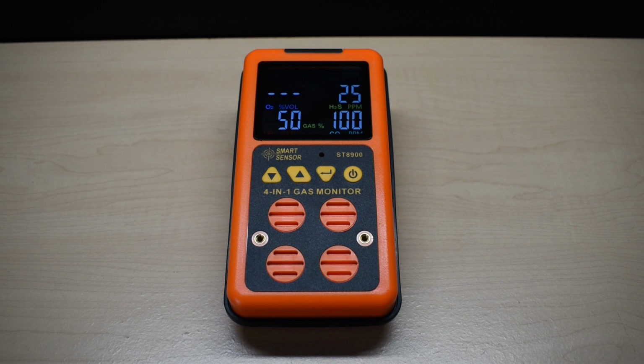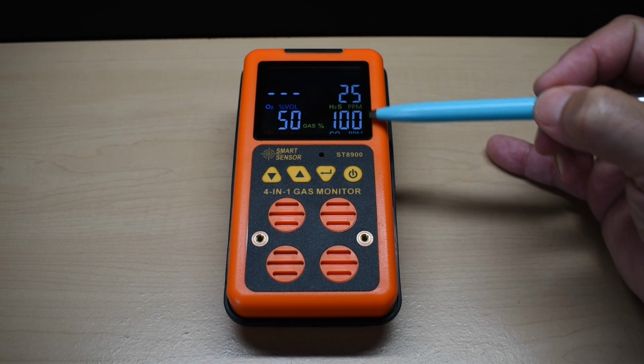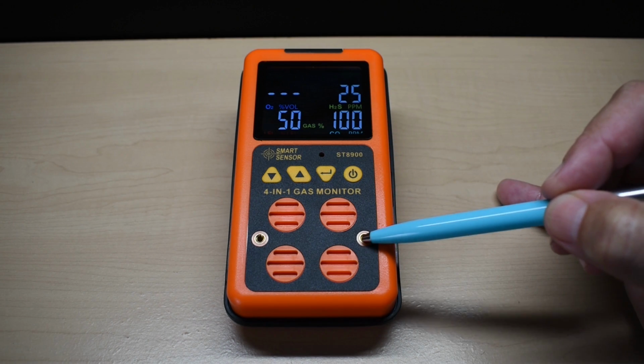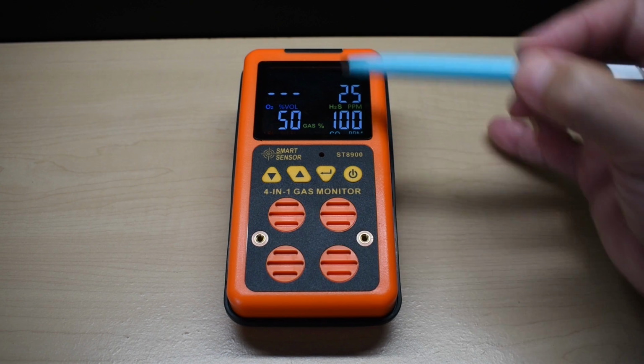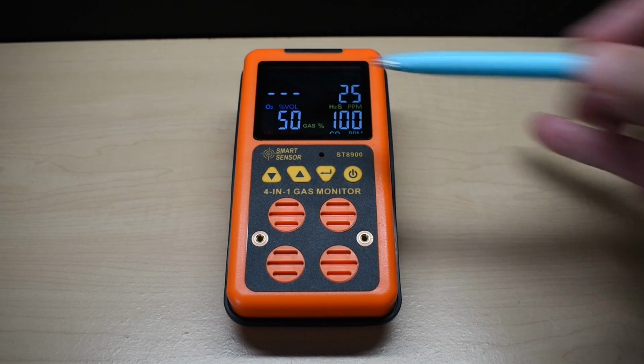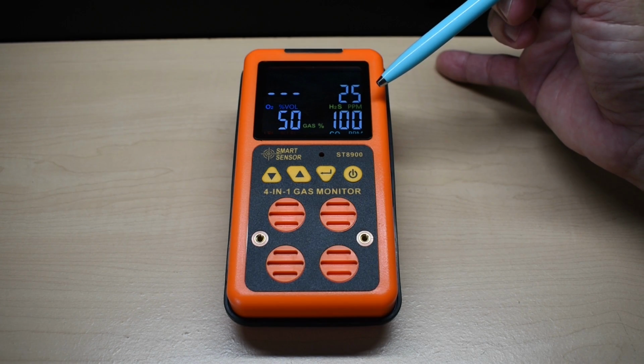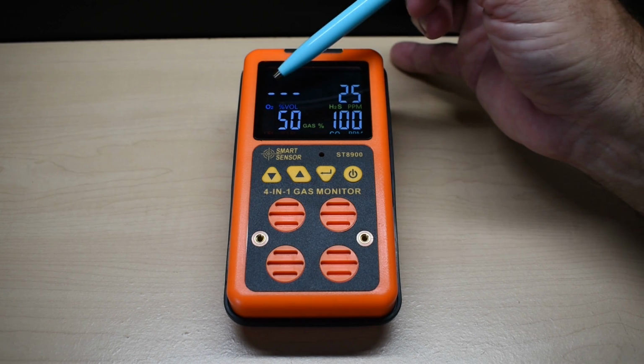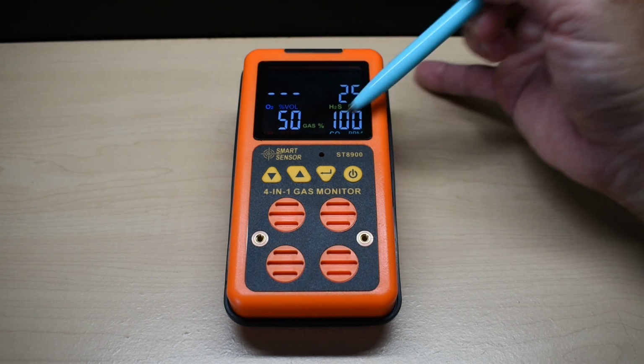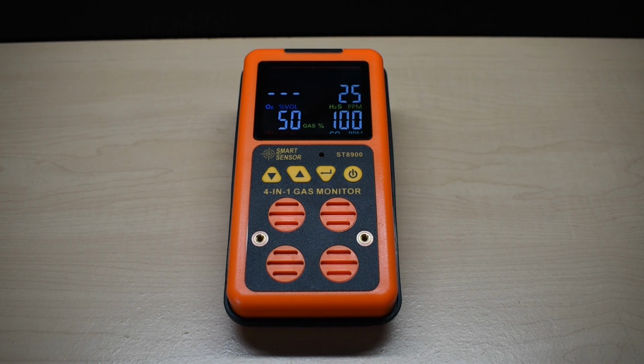Now we're into this section here. These settings here you do not want to touch unless you have the calibration sources on hand. So we're going to be concentrating on the oxygen only, and you can see in this screen right here, you can't do anything for the oxygen, only these 3. So let me move over to the oxygen.